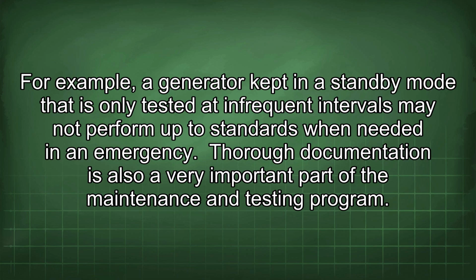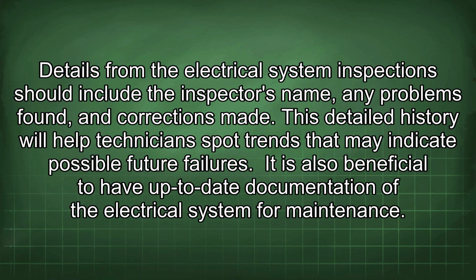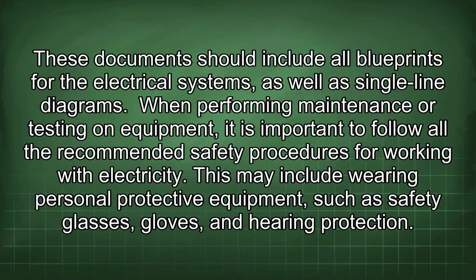Thorough documentation is also a very important part of the maintenance and testing program. Details from the electrical system inspection should include the inspector's name, any problems found, and corrections made. This detailed history will help technicians spot trends that may indicate possible future failures. It is also beneficial to have up-to-date documentation of the electrical system for maintenance. These documents should include all blueprints for the electrical systems as well as single-line diagrams.